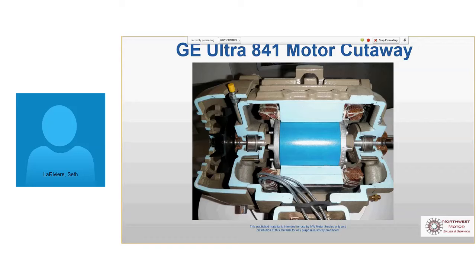All of these motors come fully greased. There's a big grease reservoir here. This is a cast iron bearing cap. GE's the only one that does that, and they use them on the front and the back. So that's these right here, and that just clamps the motor in, and they're gasketed. So in the event that somebody's re-greasing this motor and hasn't undone the grease relief on the bottom so the old grease can purge, which does happen, normally under that condition, you would just be pumping grease inside the motor when your purge is blocked or you haven't removed the fitting. With that gasket there, that makes the path of least resistance back out the shaft. So extra grease purges out along the shaft rather than back into the motor. Because when you get grease inside the motor, then it gets hot, it carbonizes, and it becomes a conductor. So that's motor failure as well.